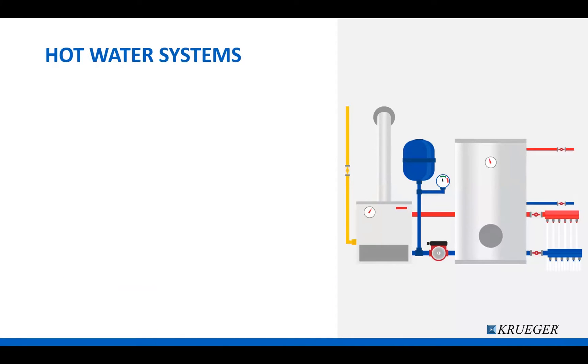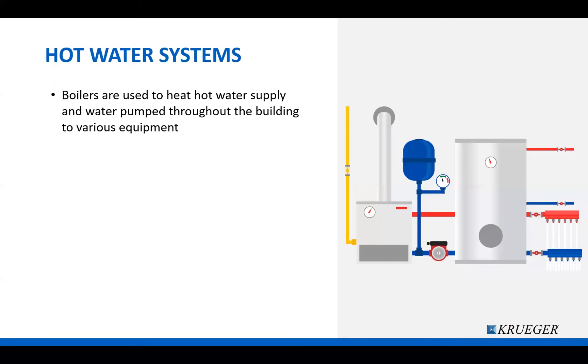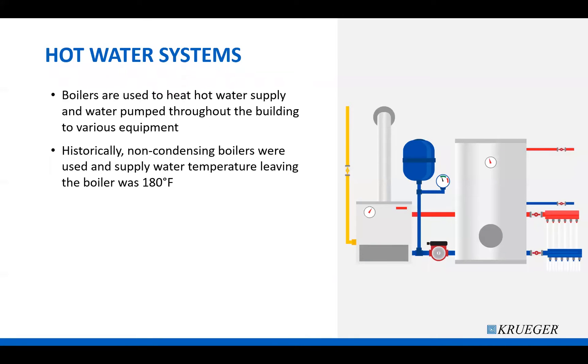Let's talk a little bit about hot water systems in general and add a little history to it. Boilers are typically used to generate heat to create hot water for buildings. This hot water is stored in a tank and then pumped to various equipment throughout the building, such as terminal units with hot water reheat coils. Historically, non-condensing boilers were used and were designed to supply 180-degree water, expecting 160-degree water to come back to the boiler.